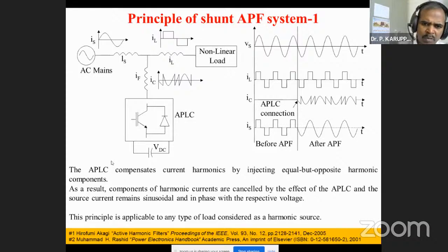Now whatever load is connected here will consume this type of current, as per the load, but the other loads connected at the same point cannot be affected. After the active power filter, whatever the load condition, the source will maintain a sinusoidal current. So that is the main concept from here. Now the question is how to design this active power filter. The active power line conditioner can be constructed using the inverter concept.